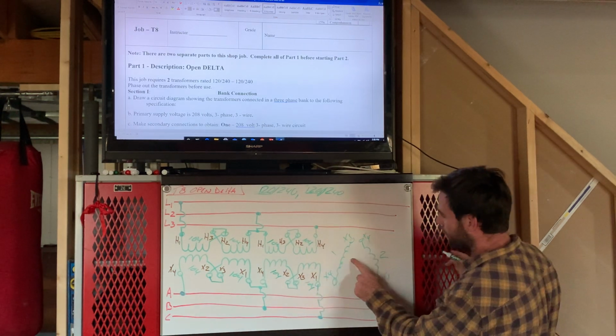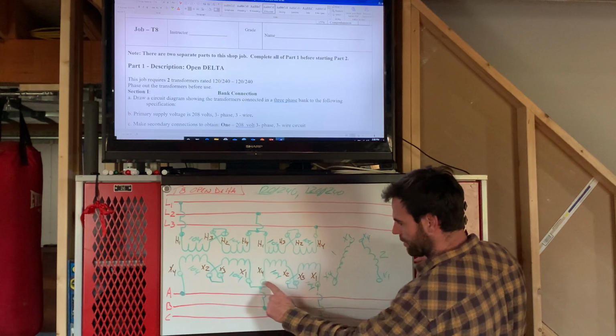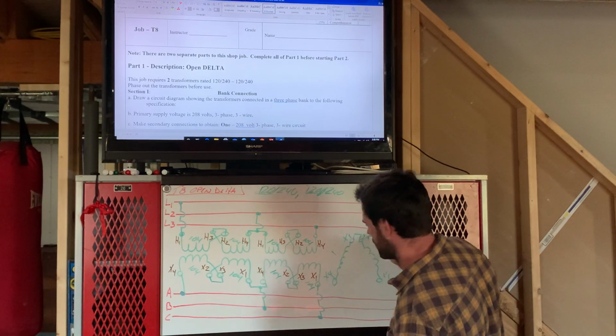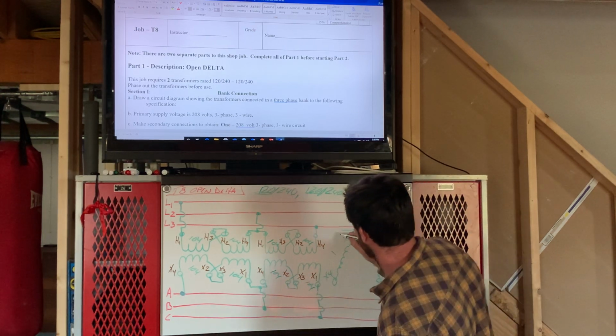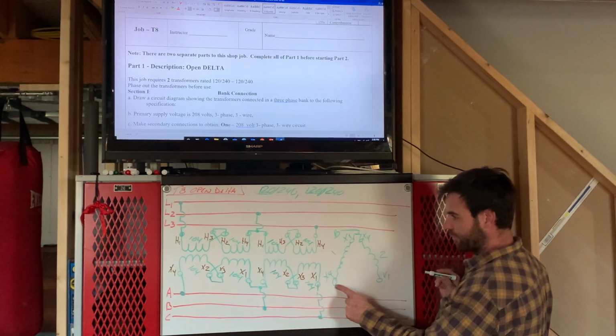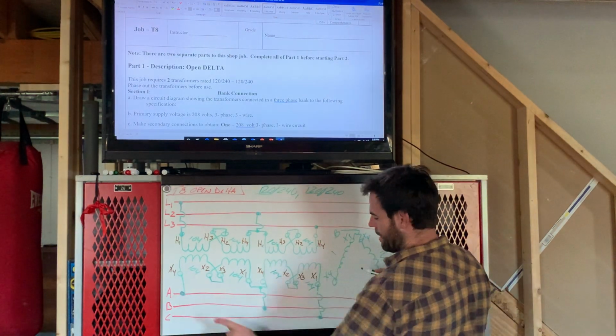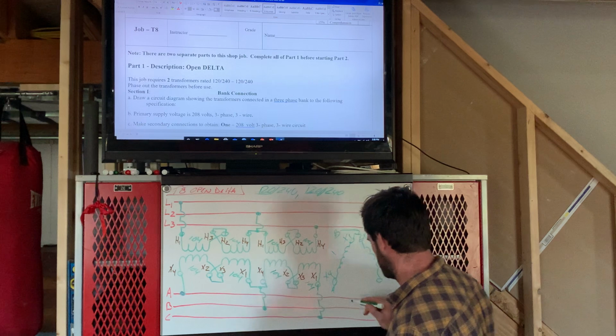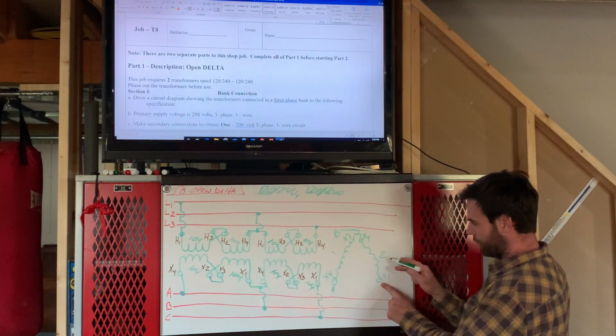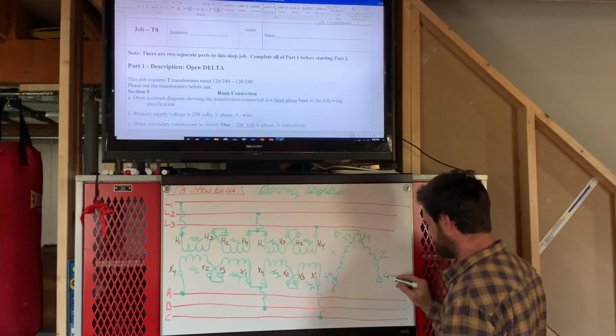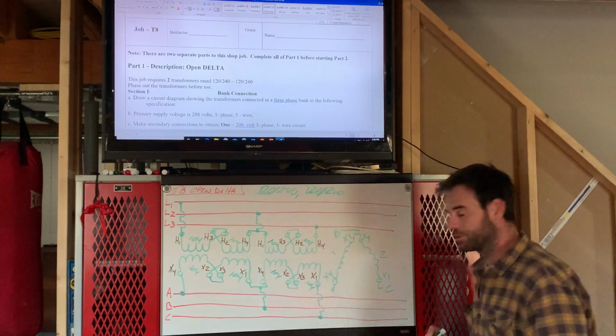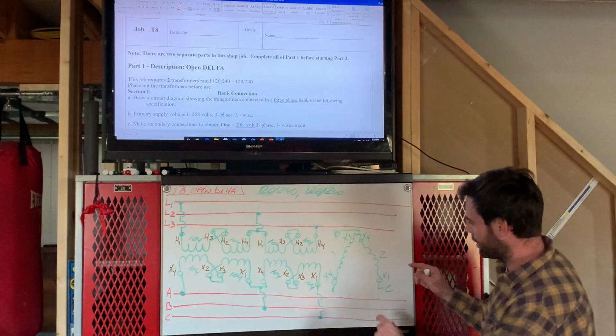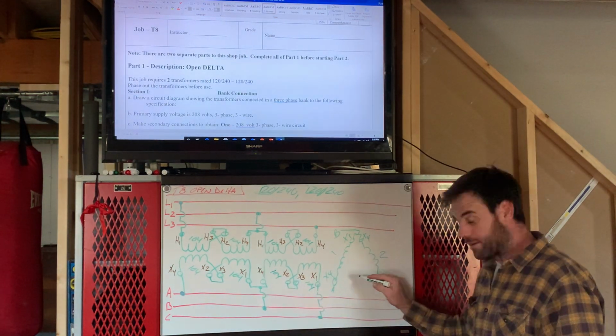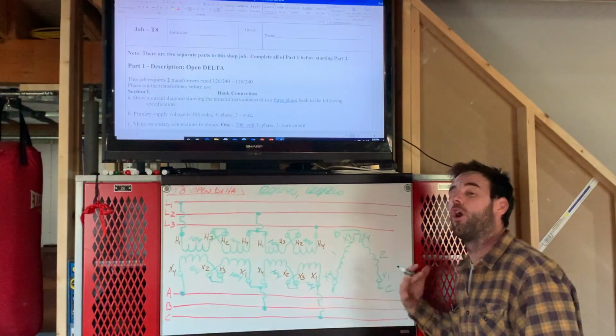So on transformer 1, X1 is jumped to X4. So here's this jumper, and that makes up my B phase. There's your B phase. X4 of transformer 1 makes up my A phase. And X1 of transformer 2 makes up my C phase. There's your C phase. They call this an open delta because the bottom side of the delta is open.